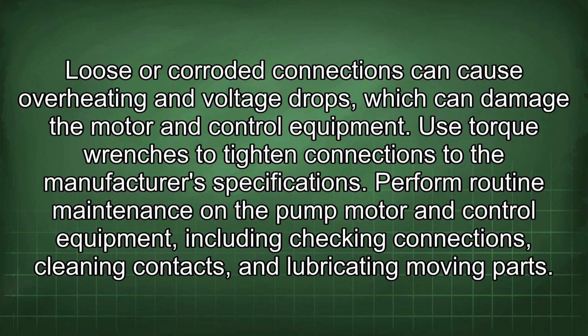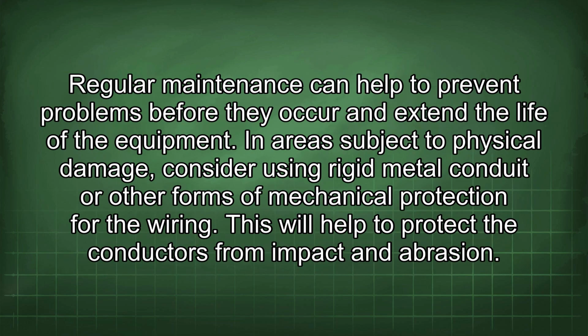Loose or corroded connections can cause overheating and voltage drops, which can damage the motor and control equipment. Use torque wrenches to tighten connections to the manufacturer's specifications. Perform routine maintenance on the pump motor and control equipment, including checking connections, cleaning contacts, and lubricating moving parts. Regular maintenance can help to prevent problems before they occur and extend the life of the equipment.